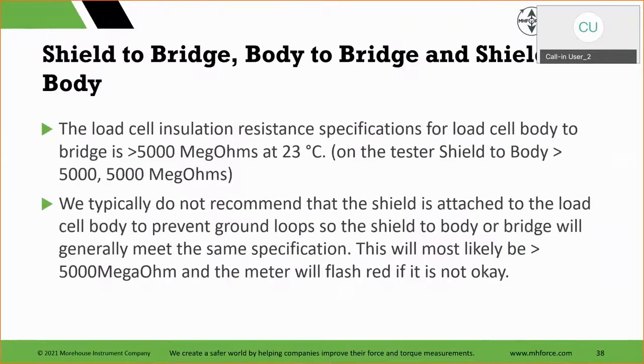And then here's where we get to the mega ohm reading here. Load cell insulation resistance specification for load cell to body bridge is usually greater than 5,000 mega ohms at 23C. On the tester, shield to body greater than this. We typically do not recommend the shield is attached to the load cell to prevent ground loops, so the shield or body generally meet the same specification. All that saying here is when we power this up, and if you want to use this, you make your own cable, and typically we put one cable with an alligator clip that can be connected to the different input on the load cell tester, and then you connect that to the load cell. So you fire it up, do your test, then fire it up and hook the alligator clip on, and you can do these other tests that way.